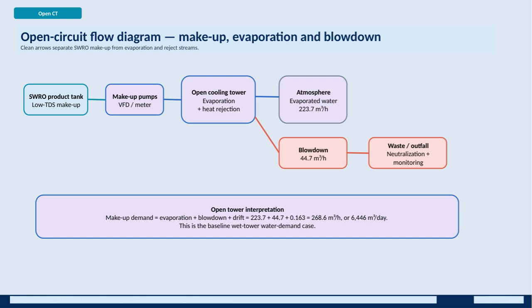The open tower's water demand is the sum of evaporation, blowdown, and a small amount for drift loss, totaling approximately 268.6 cubic meters per hour, or just over 6,400 cubic meters per day.